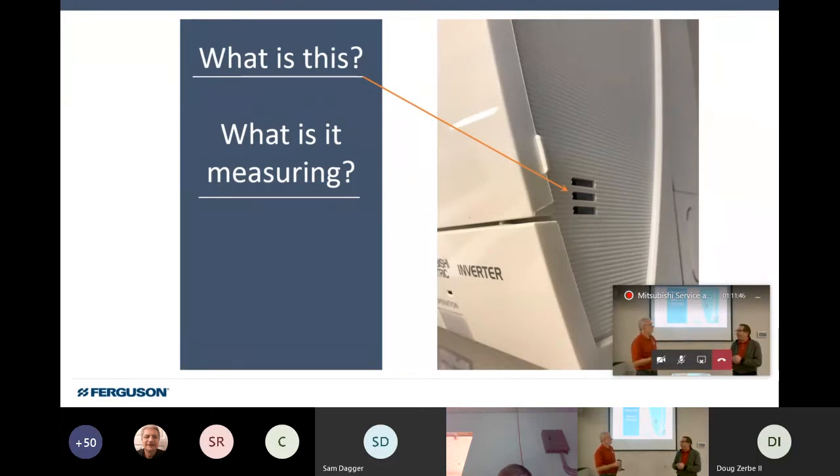Right. And now all of a sudden, we're going to have to disable that sensor. We're now going to have to put an MHK one in here where we're sensing more in the room space, not because of the offset. There's nothing we can do about that offset on that piece of equipment.